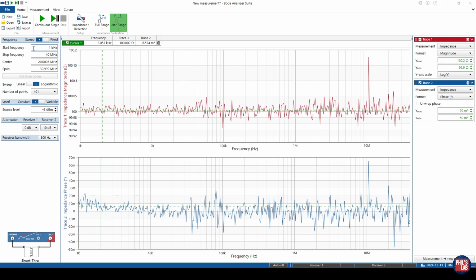In terms of measurement setup, my start frequency is 1 kHz. I set this deliberately a bit higher because it's still well within the measurement range, but above any potential DC biased cutoff frequency, high-pass filter effects of the DC blocks. I'm going up arbitrarily to 40 MHz so we can still capture information on the self-resonant frequencies of these small multi-layer ceramic capacitors.